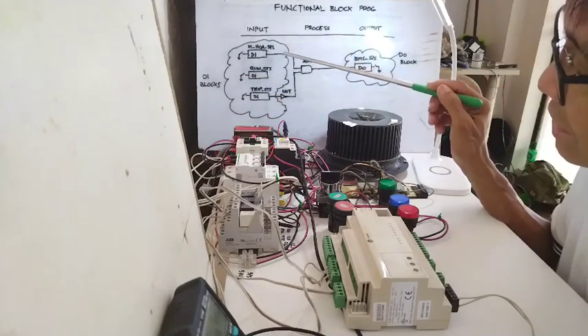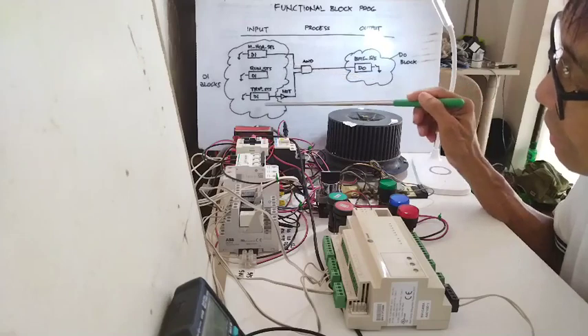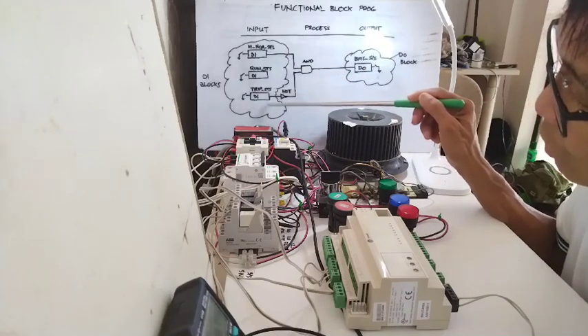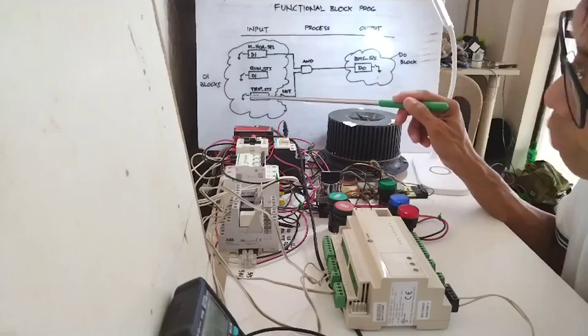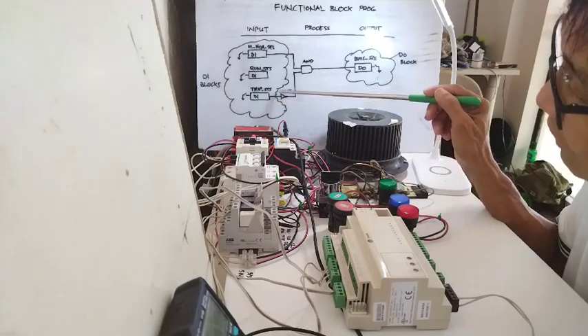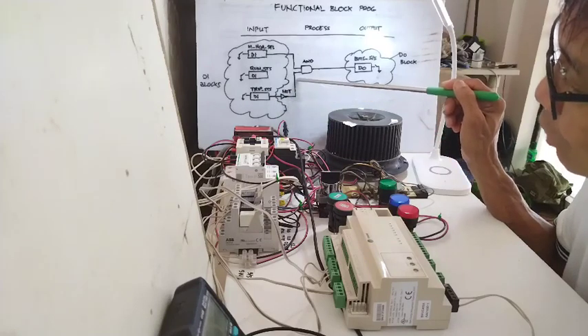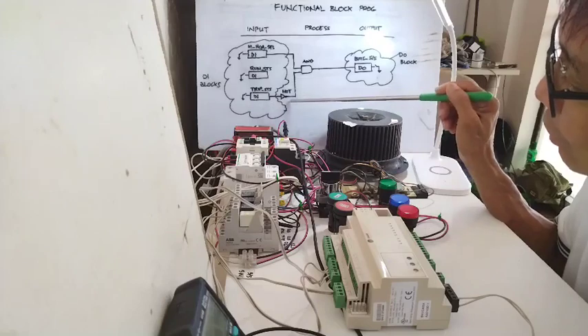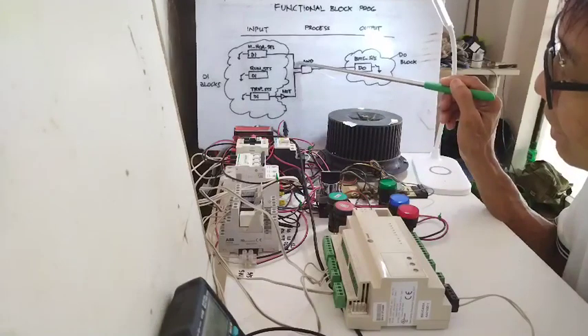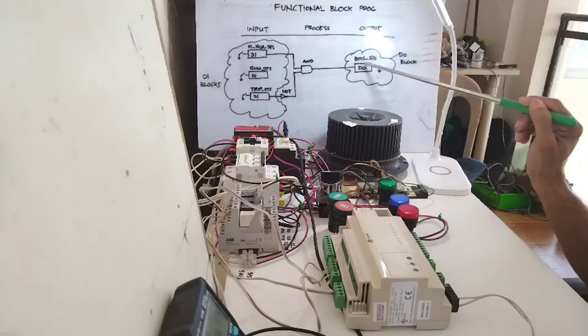It should be in auto and there's no trip — so the trip signal is 0. Because if it trips, it becomes 1; so when there's no trip, it is 0. That 0 is fed to the NOT gate and inverted to 1, giving input B of the AND gate a value of 1. So I have 1 and 1 at the AND gate inputs, and the output will be 1, which then goes to the DO block.